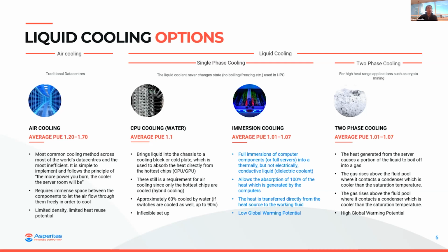There are different options within this space, and we can make a comparison with air like we see now on screen. Very simply put, there's a single phase cooling category, water cooled, direct-on-chip solutions, immersion cooling in different shapes and formats - let's use that as one category. And there's two-phase immersion cooling as well, which has benefits on the performance end, maybe even beyond what we see now as a practical application. But the real downside there is global warming potential.